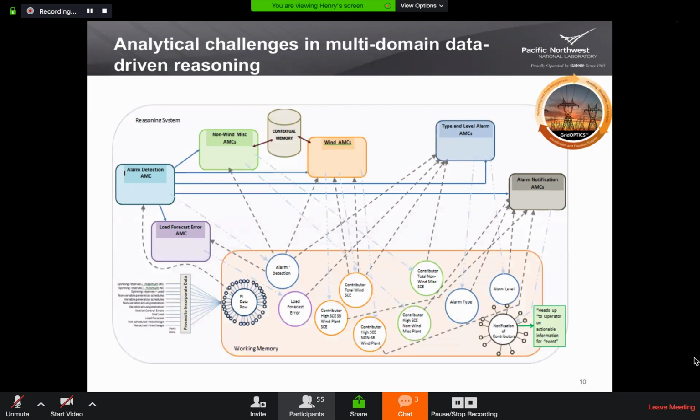Let me give you maybe a quick simple example. For example, if you observe on your screen that your voltage dropped to 0 from 500 kV, the alarm went off, and without any other information, of course, everyone would think, oh, maybe that's an outage somewhere. So maybe a short circuit, that's why the voltage dropped to 0. Now that may or may not be true, but if you don't have any other information, that's probably the only thing you can reason about.